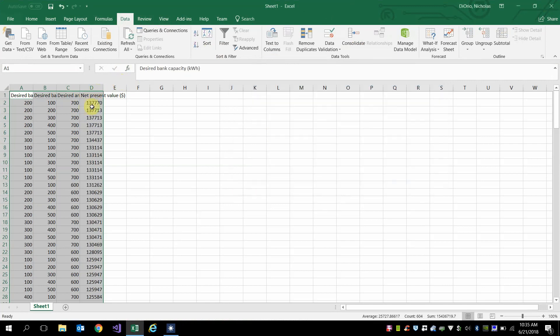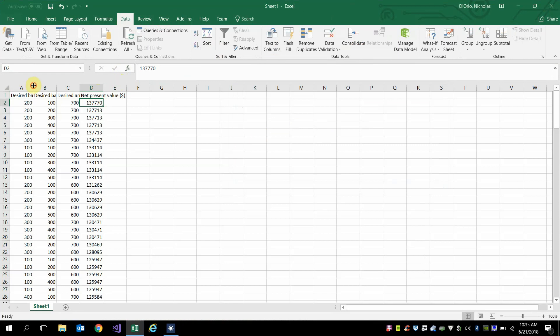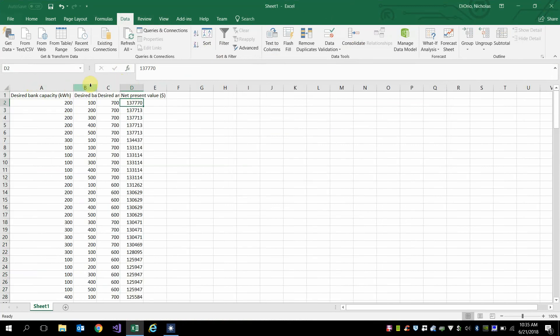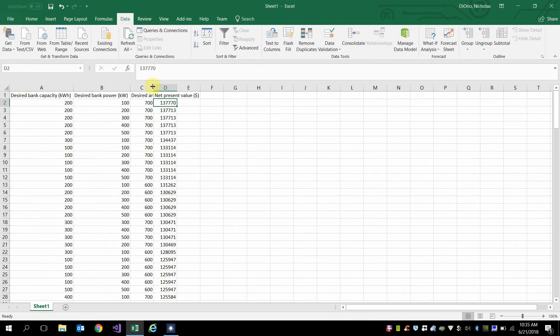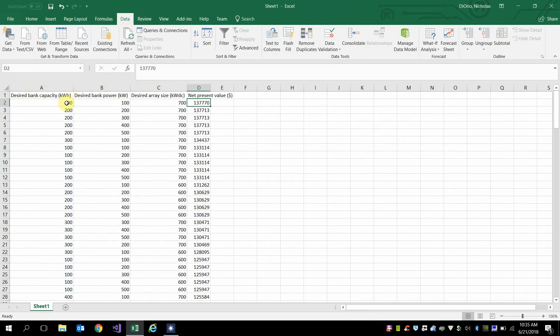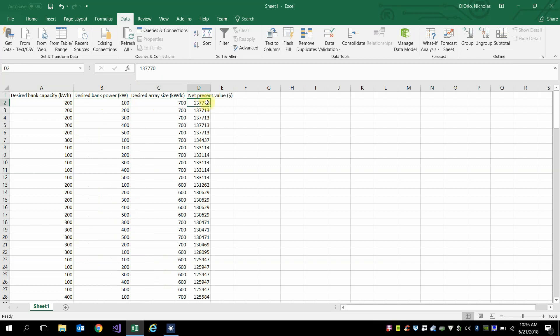And here this is going to show you that for a certain size of system, in this case a 200 kilowatt hour battery, a 100 kilowatt of battery power, and then a 700 kilowatt PV system is going to maximize your net present value.